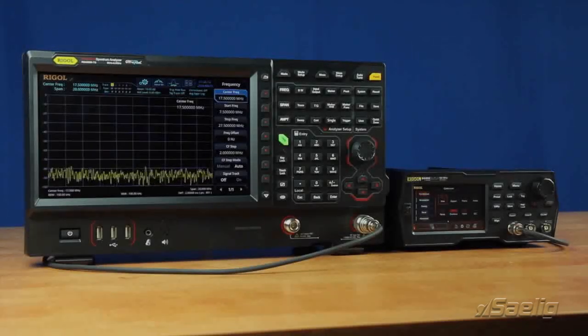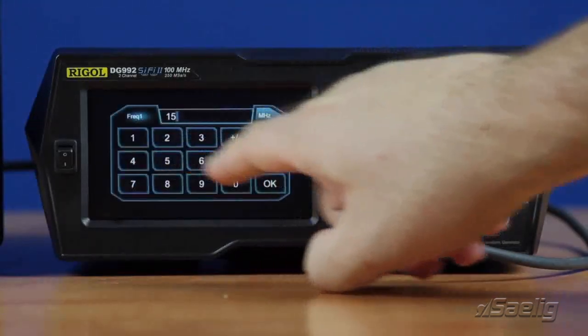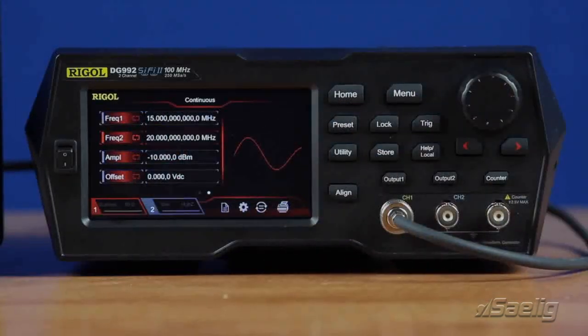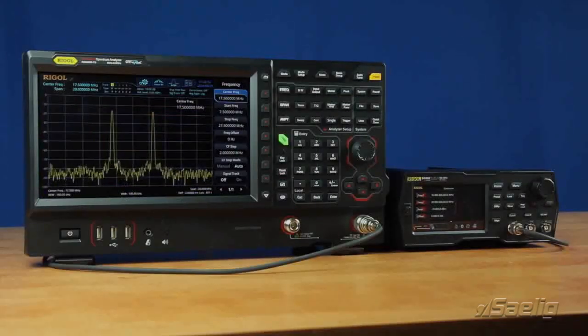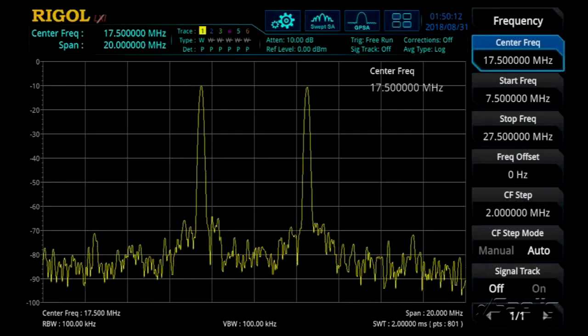The DG800 and DG900 series arbitrary waveform generators both come with a built-in dual-tone function, which allows you to create an ever more complex signal by being able to choose two different frequencies — useful for filter testing. To use this function, go into the dual-tone section of the continuous menu, set the first frequency — for example, 15 megahertz — and then the second frequency, say 20 megahertz. With amplitude set to negative 10 dBm, you can also choose an offset. Turning the output on and connecting to a spectrum analyzer, we can see the two different frequency tones on the display centered around the 17.5 megahertz center frequency.